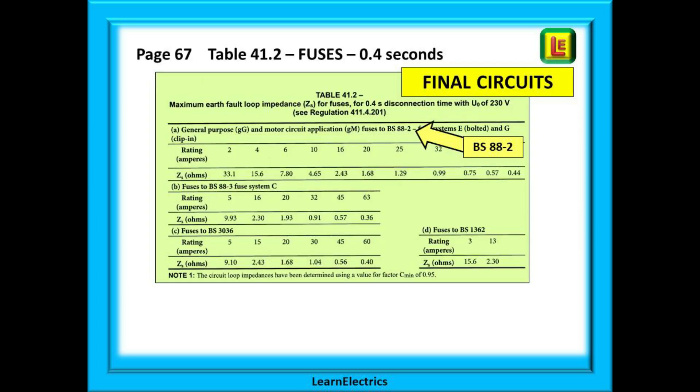Looking at the ZS tables now and answering the question, what is the maximum ZS impedance permitted, we will begin with table 41.2 on page 67, which is for fuses only. It tells us it is for 0.4 second circuits, which implies final circuits only, and you must remember this. There are four types of fuses shown. BS88-2, BS88-3, and notice here that the fuse sizes shown do not exceed 63 amps.